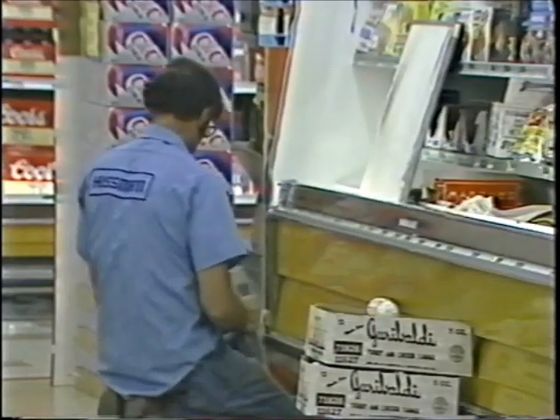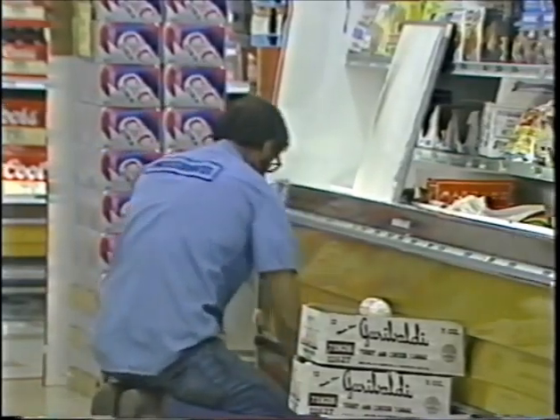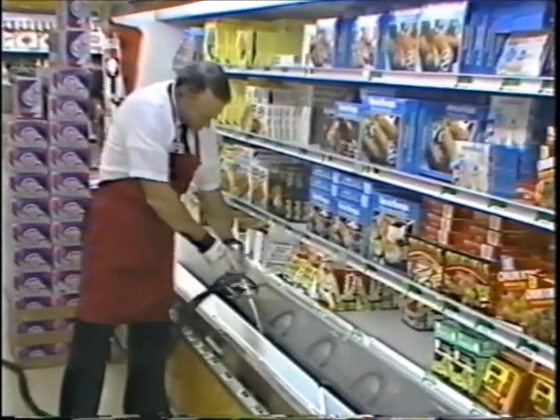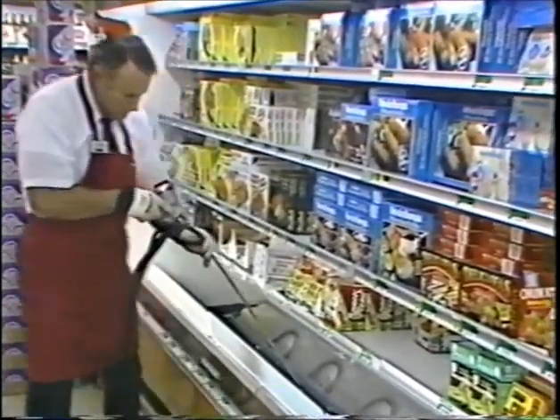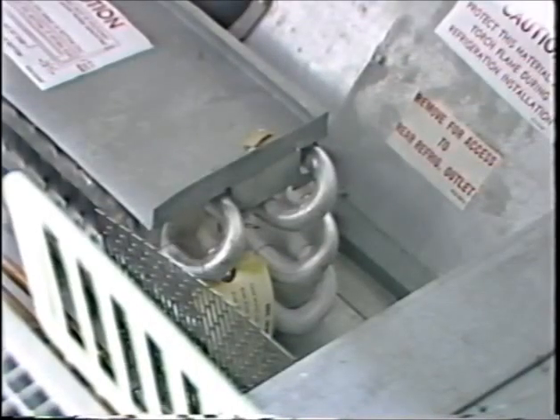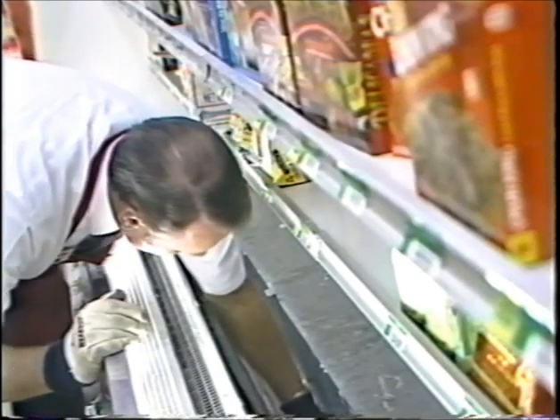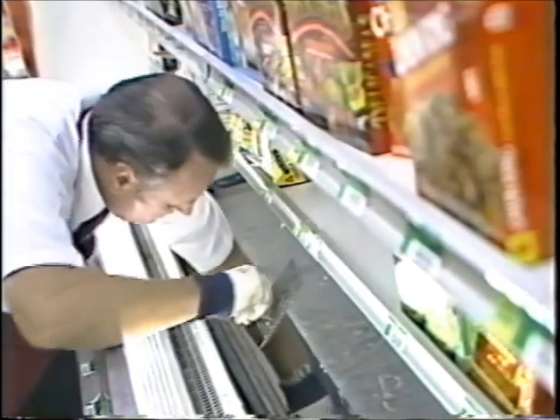Equipment sometimes requires periodic service from an outside source. However, most parts of the preventive maintenance program can be performed by store personnel. An iced-up coil is the most common reason for a service call. The cause is usually a stopped-up drain located in the bottom of the display case. If display cases are not cleaned on a regular basis, price tags, price labels, product spills, and wrappers will collect in the drain.